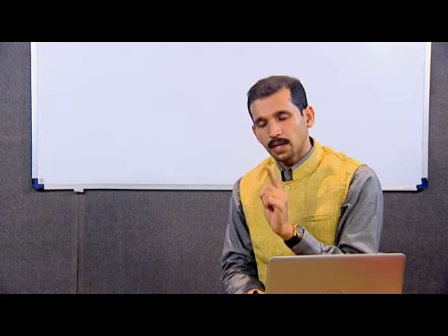As you see in the table, there are very specific K beta filters, as they are called, for specific tubes. For example, in the copper tube we use a nickel K beta filter. So, with the help of these filters we cut away the K beta, and then there will be K alpha 1 and K alpha 2.